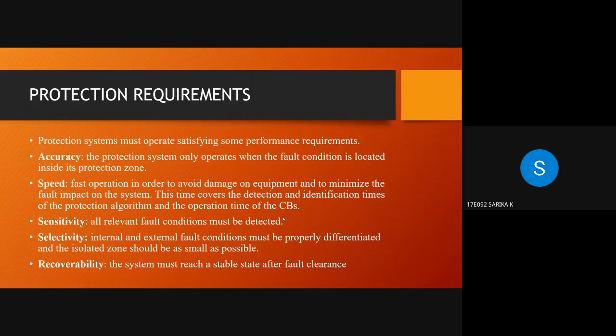In accuracy, the protection system only operates when the fault condition is located inside its protection zone. In speed, fast operation is needed in order to avoid damage on equipment and to minimize the fault impact. This time covers the detection and identification times of the protection algorithm and the operation time of the circuit breakers. In sensitivity, all relevant fault conditions must be detected. In selectivity, internal and external fault conditions must be properly differentiated and the isolated zone should be as small as possible. In recoverability, the system must reach a stable state after fault clearance. These are the protection requirements.